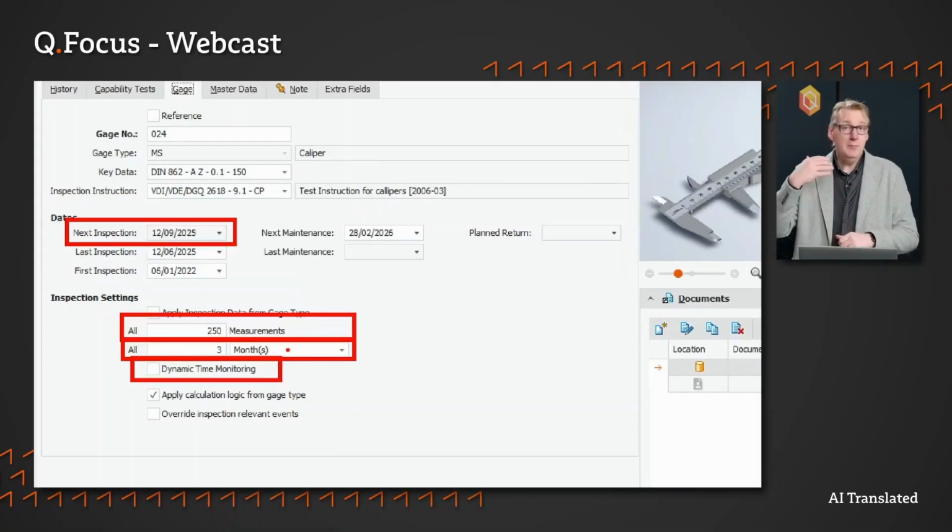You have a measuring instrument storage area where the instrument is hardly used at all. Then you can have the system automatically extend the inspection interval from 3 months, for example, to 6 months. And these are the automated processes that are meant to benefit you not by sticking rigidly to the 3 months interval, but by making it dynamic depending on how intensively the measuring instrument is used.